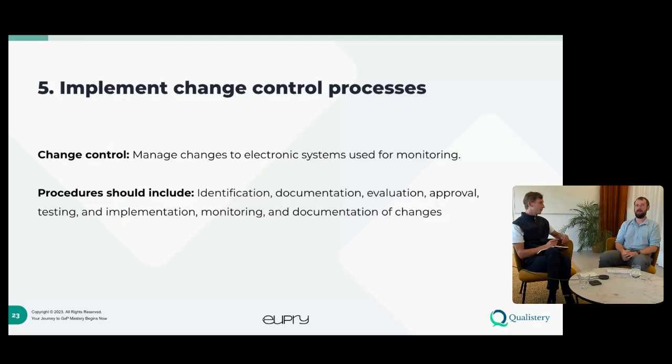Another requirement from Part 11 is that you implement change control. As with all other systems in a GXP environment, you need to implement change control. Whenever there's an update to a system or an update to how you use the system in a compliant way, you need to make sure that you have change control in place.